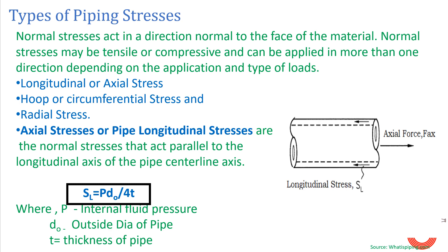The different types of stresses in a piping system begin with normal stresses, which act in a direction normal to the face of the material. Normal stresses may be tensile, compressive, or act in more than one direction depending on the application and type of loads. Normal stresses are divided into three parts: longitudinal or axial stress, hoop or circumferential stress, and radial stress.